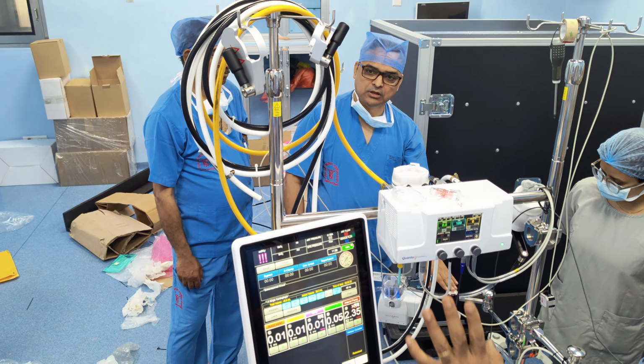We have programmed this channel to give you the venous flow directly. So whatever the venous flow coming from the patient to the oxygenator, it will show 4 liter, 5 liter, 6 liter, 3 liter, whatever. As soon as the level drops, the venous line will give you an indication that it was 4 liters and now it has become 2 liters. So if you have kept this at a level, the pump automatically senses the venous flow, it will warn, and the arterial pump will immediately slow down to the venous return flow.